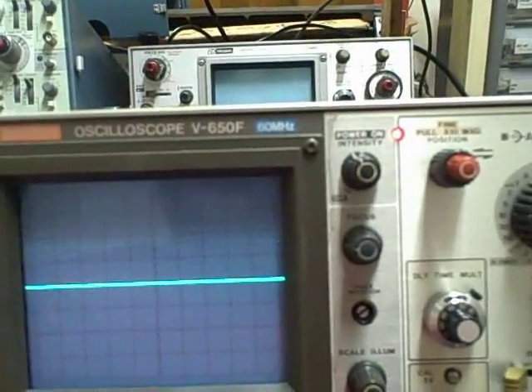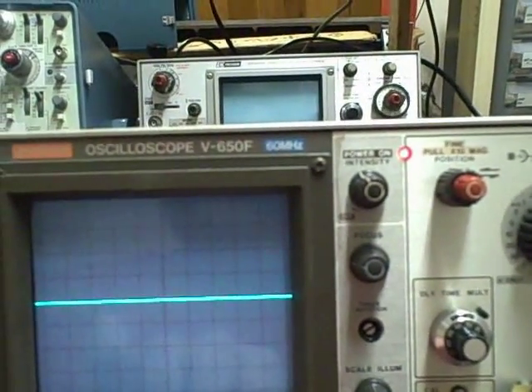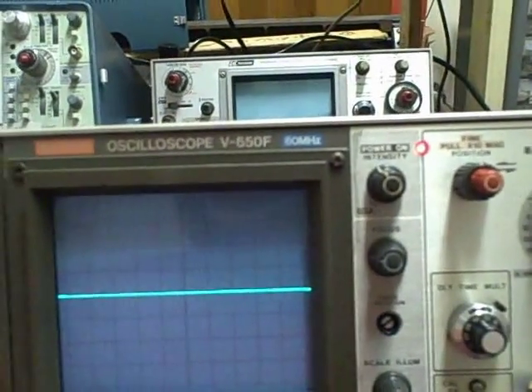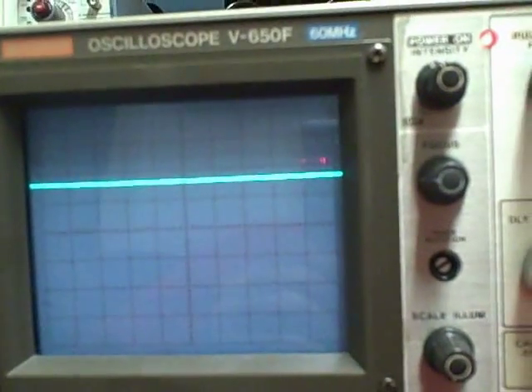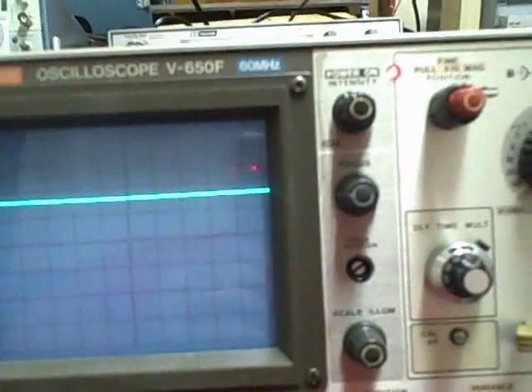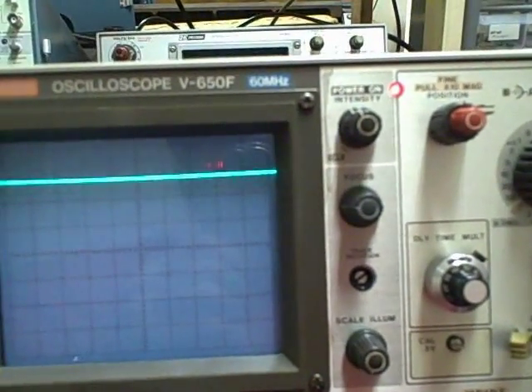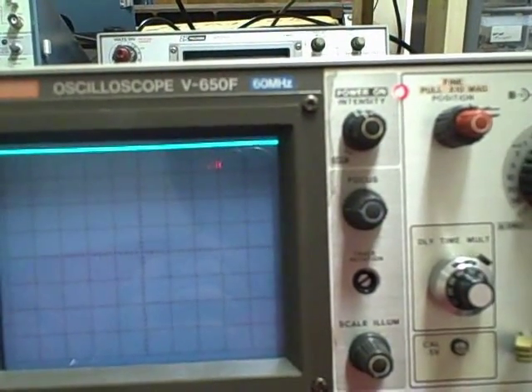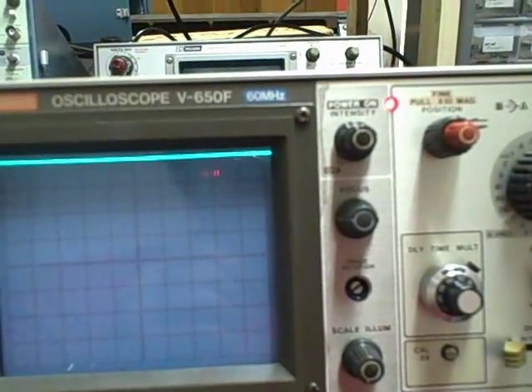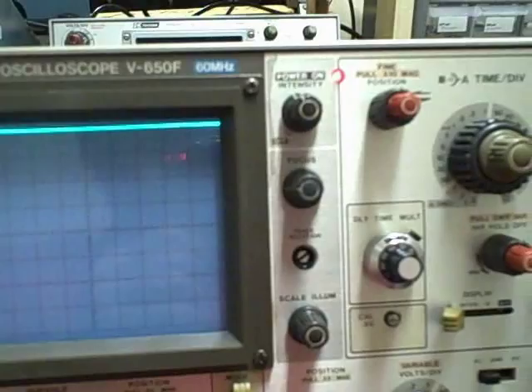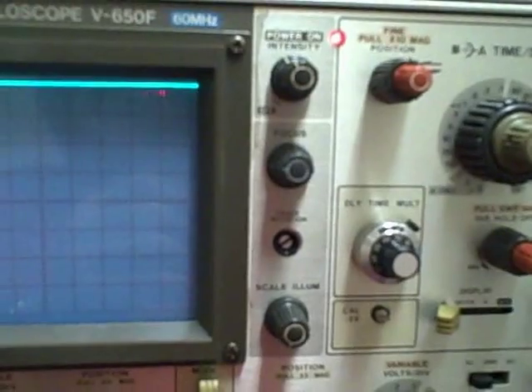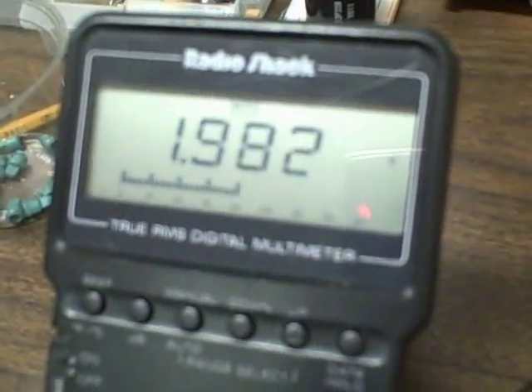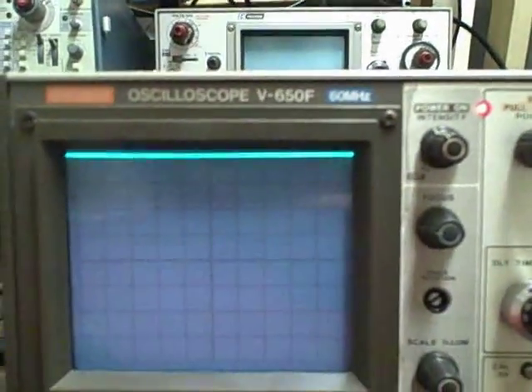Okay, let's change to 0.5 volts per division. And we are one and a half divisions up, roughly, again. I'm going to take her up to full scale. I would say that looks to me to be full scale. 0.5 volts per division, four divisions, 0.5 times four would be two volts. And we are reading 1.982. So we're within a little less than two hundredths of a volt. We're there.